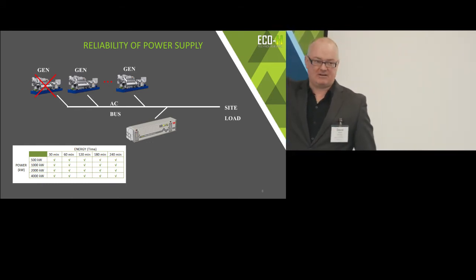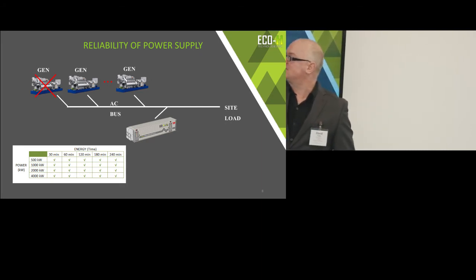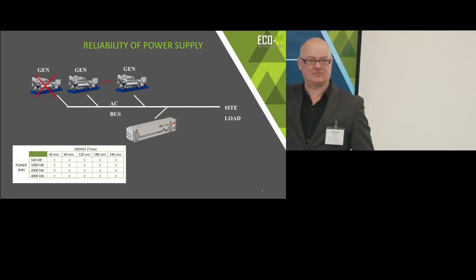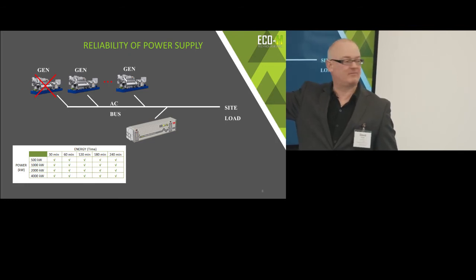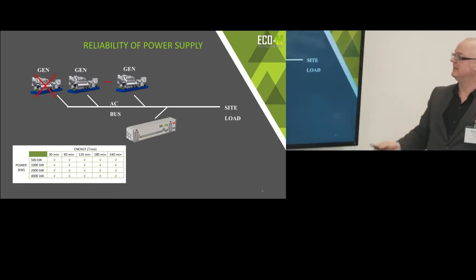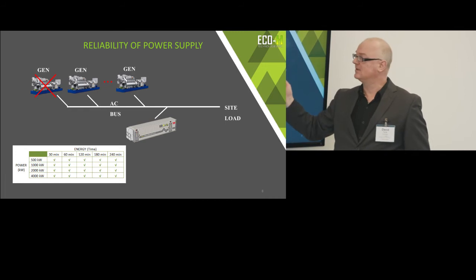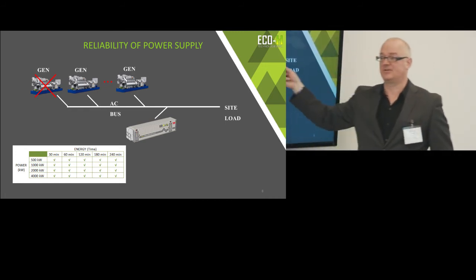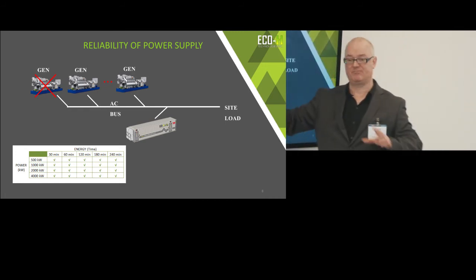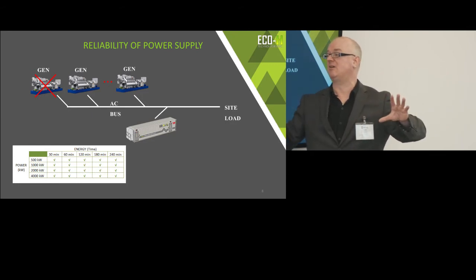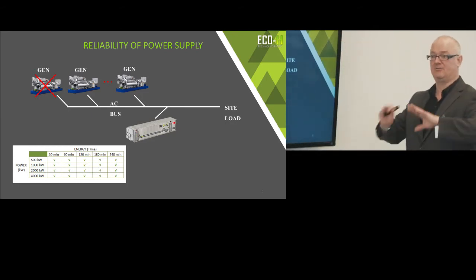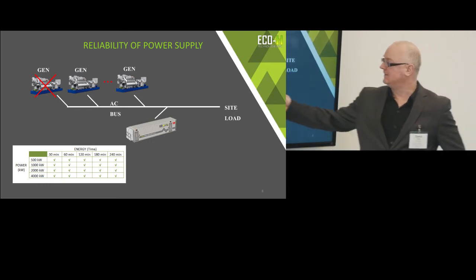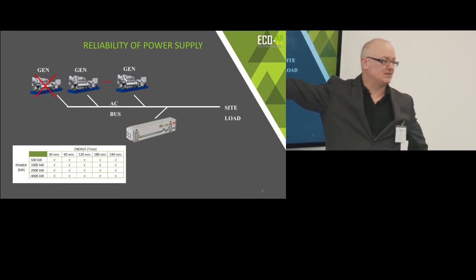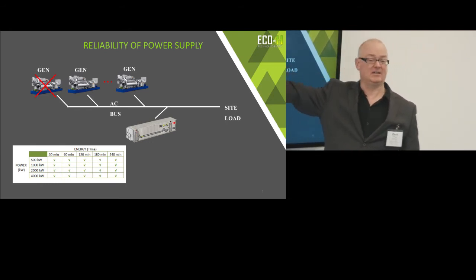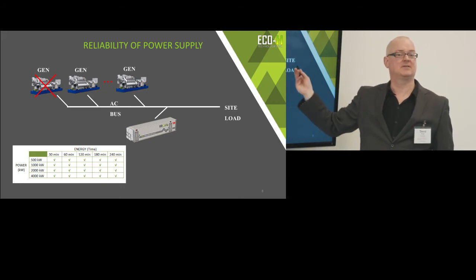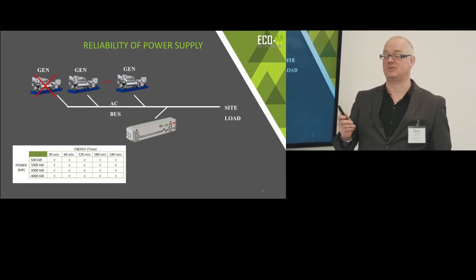Energy storage and generators on a typical site. One's out for maintenance, and depending on the site's load capacity, you could have 3, 4, 5, 6 megawatt generators to feed the standard AC bus. This is just an AC line bus for those of you that aren't electrical. It's just a big copper bar, a bus bar, everything's powered from there. All to the circuit breakers, to the loads, to the machines, to everything else. If one of these drops out for any reason and there's a fault on the system, then immediately you would lose a lot of power on the AC bus. So straight away, a lot of your systems would start to crash.